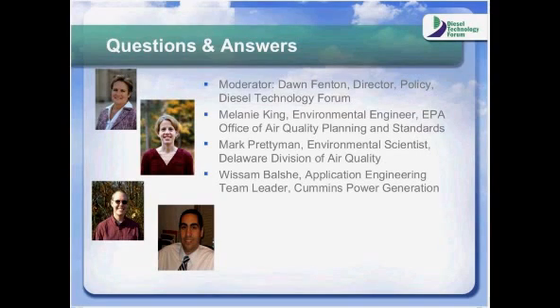So the model rule as it is now, this gets to another question. So it is more stringent than the federal government's NSPS? Only in the sense that the Tier 4 non-road rules apply by various power ranges. I can't think of exactly what the different power ranges are. They are broken off in horsepower or kilowatt sizes of the engines. The standards that were listed are one specific power range, which is the most common range and the most stringent of the different power ranges. It's not more stringent than what's listed. It's just the most stringent of the different power ranges. I understand. Okay. All right. Great.